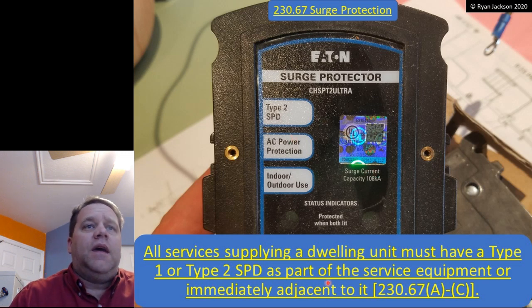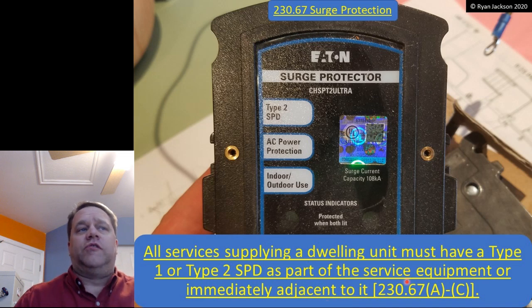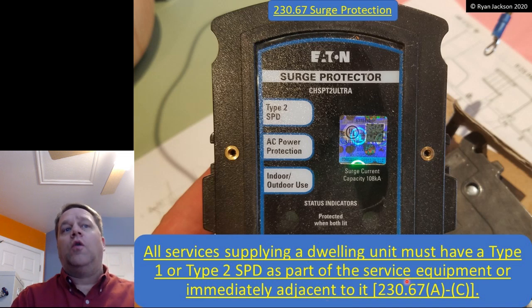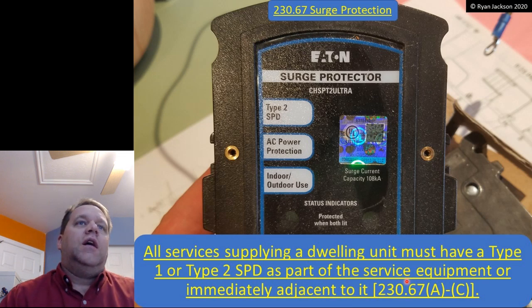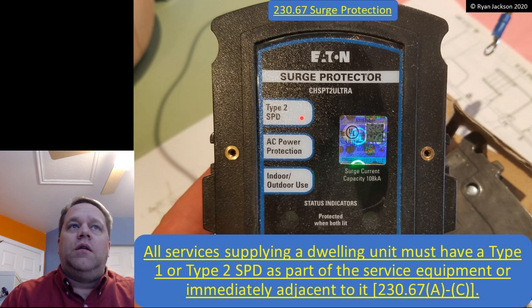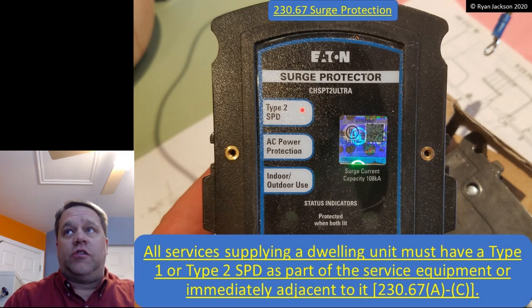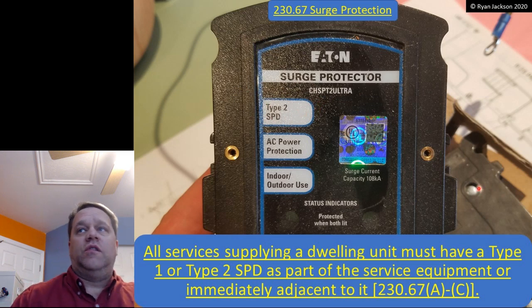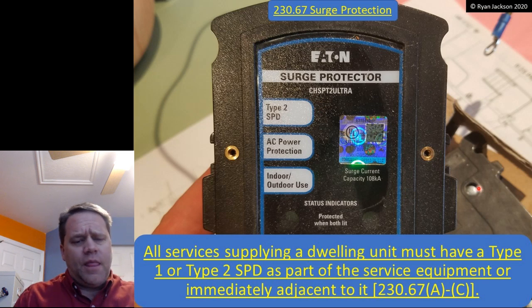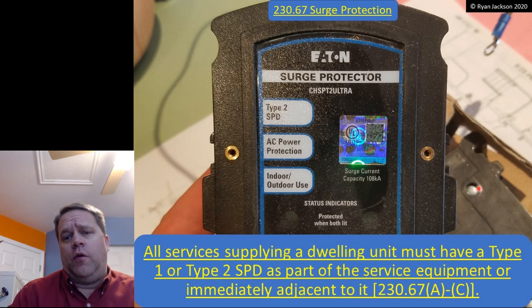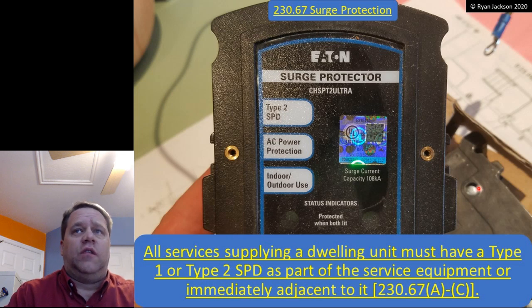So it has to be either a Type 1 or a Type 2 surge protection device. And again, it has to be part of the service equipment, so part of the service disconnect or right next to it, immediately adjacent to it. If it's in the service equipment, it might be a Type 1 if it's installed before the breaker or fuse. If it's installed afterward, it would be like the one in the photograph, a Type 2 surge protection device. So I've got to have a surge protection device for all dwelling unit services.